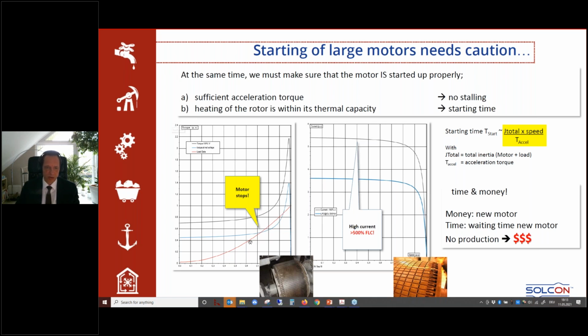What if not? What you see here on this graph is the starting torque of a motor at full 100% voltage or at reduced voltage. And here you see the torque speed curve of the driven machine. Here, the two curves meet and the motor will stop here. When the motor is stopping here at 0.7 or 70% of the speed, you still have a high starting current, over 5 times. And this means if this is applied for too long a time, the rotor will burn and you have quite a damage on the motor, which will cost a lot of money.